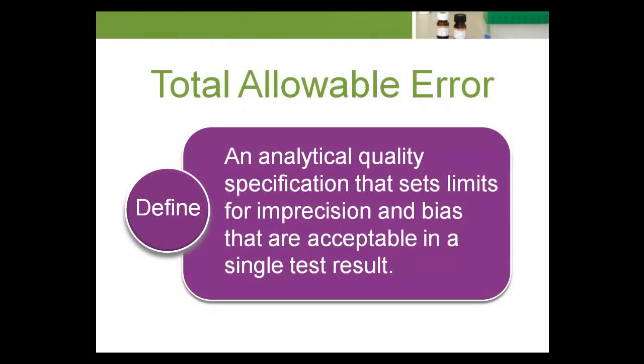Total allowable error TEA is an analytical quality specification that sets limits for imprecision and bias that are acceptable in a single test result. It's a process control tool based on human biological variation data and can be used as a secondary feedback mechanism for statistical process control analysis.